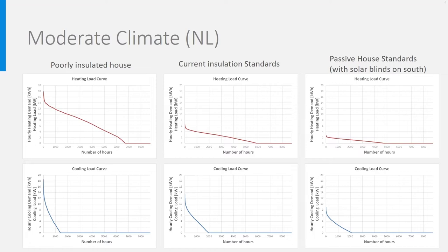The scale is identical on all graphics so you can see how important the physical design of the house is. You can make the most fantastic HVAC design on a poorly insulated house, using for instance a heat pump of 6 kW and a gas boiler of 12, but the energy usage will still be much higher than it could have been if you had insulated the house. You also see that the number of hours where heating is needed decreases with insulation.